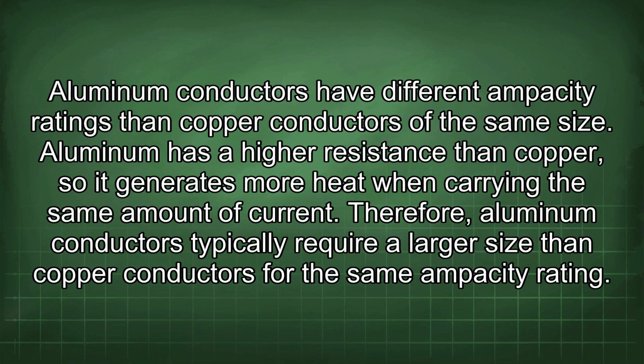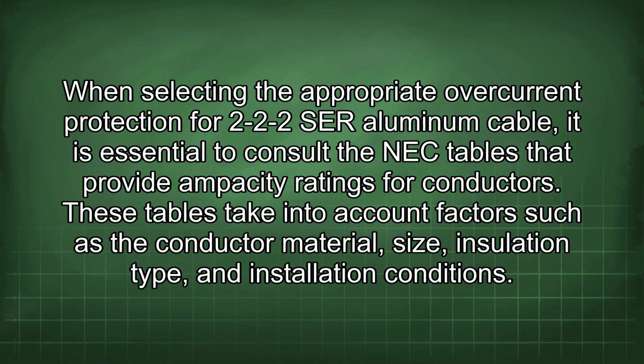Aluminum conductors have different ampacity ratings than copper conductors of the same size. Aluminum has a higher resistance than copper, so it generates more heat when carrying the same amount of current. Therefore, aluminum conductors typically require a larger size than copper conductors for the same ampacity rating. When selecting the appropriate overcurrent protection for 2-2-2 SER aluminum cable, it is essential to consult the NEC tables that provide ampacity ratings for conductors.